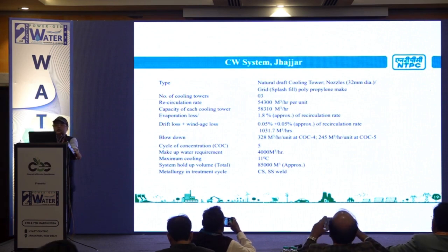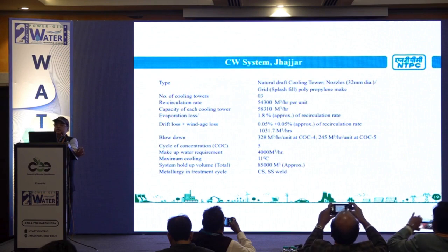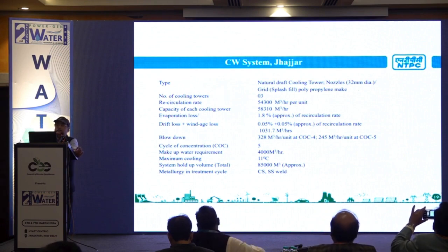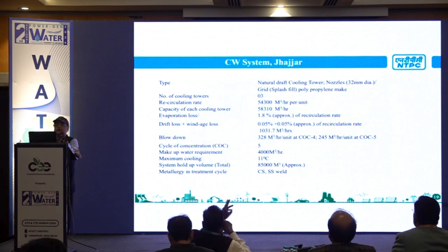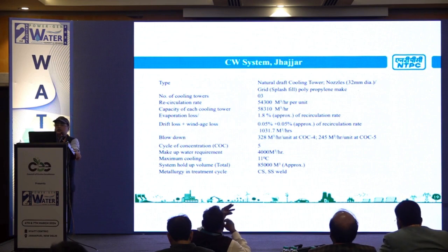Here are some of the parameters for the CW system in the Jhajjar. We have 3 NDCT natural draft cooling towers, and our circulation rate is 54,000 meter cube per hour per unit. These are all the parameters, and we are measuring through 5 to 6 COC.